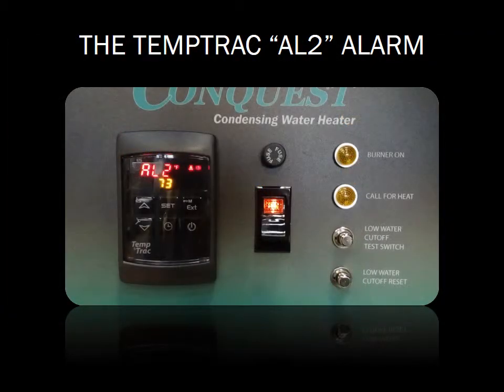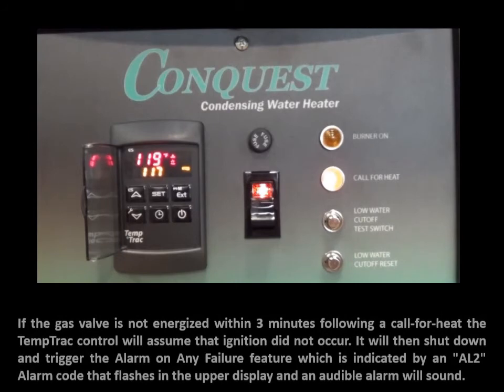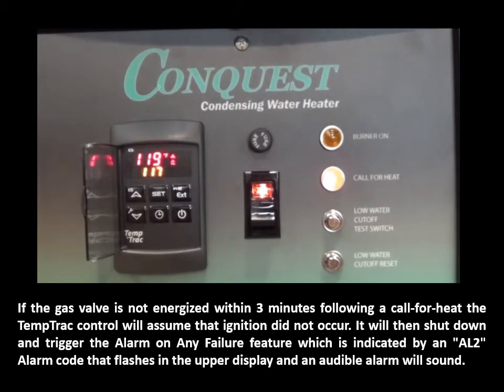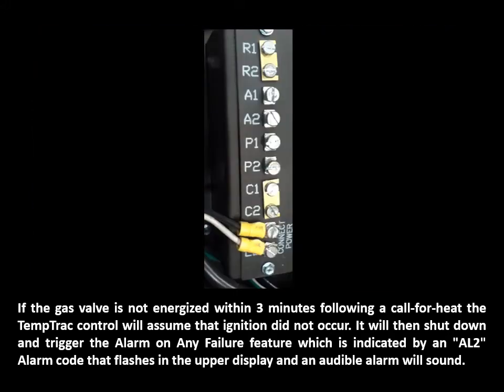Although the digital input 2 alarm function is activated when the Temptrac control is energized, it is only monitored during a call for heat. Following a call for heat, digital input 2 is deactivated when the gas valve is energized. If the gas valve is not energized within 3 minutes following a call for heat, the Temptrac control will assume that ignition did not occur. It will then shut down and trigger the alarm on any failure feature, which is indicated by an AL2 alarm code that flashes in the upper display and an audible alarm will sound. A large flame icon will also illuminate to indicate the internal output 2 alarm relay has energized Temptrac terminals 6 and 7 to enable the field access alarm terminals A1 and A2.